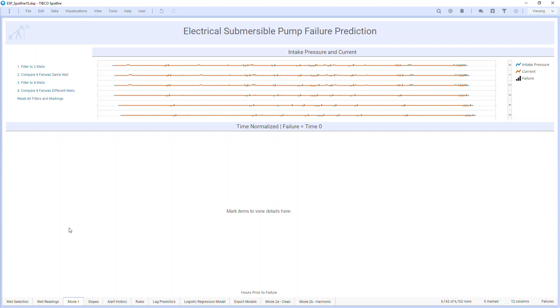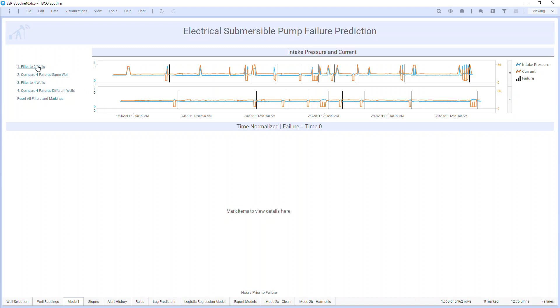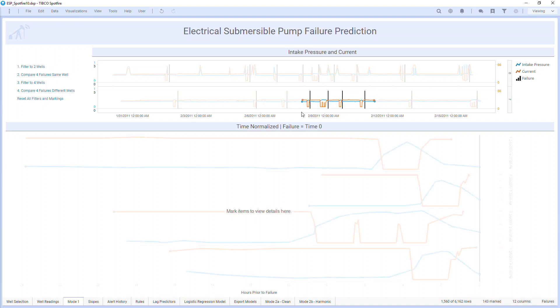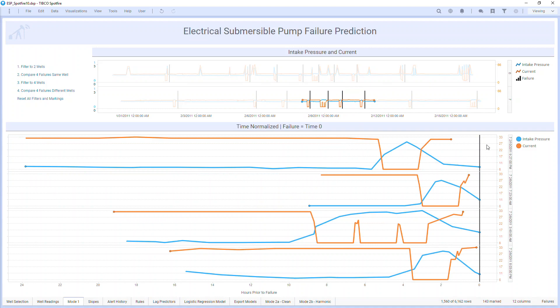Now let's investigate these failures a bit further. Here I have pressure and current data overlaid for the failed wells. Looking at a couple wells side by side, you'll see these black vertical lines, which are logged events for when my pump failed and the lift system shut down. I'll grab a few failed regions on a single well, and Spotfire aligned each of these failures to zero at the black line on the right, then plotted the sensor data in the hours leading up to the failure event. In each of these, I see a drop in current, all associated with an uptick in pressure.